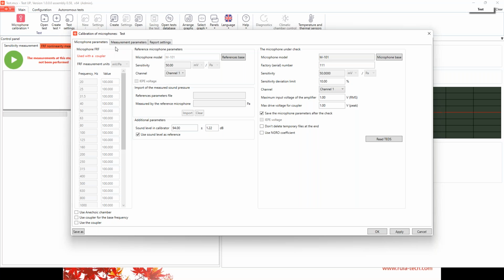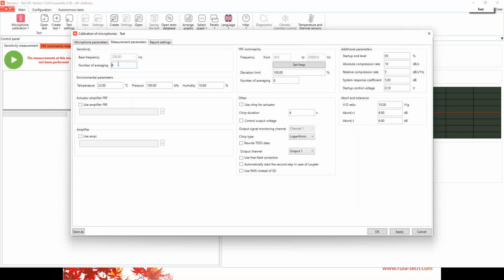After that, we go to the next step with measurement parameters. Here we have our base frequencies, 250 Hertz, and the number of averaging. I don't want this calibration to go for a long time, so let's enter 4. Here you enter the environmental parameters like temperature, pressure, and humidity. Sorry, if you want, you can enter the actuator and the amplifier FRF. Here we select no. Here we enter the frequencies for FRF only linearity calculations.